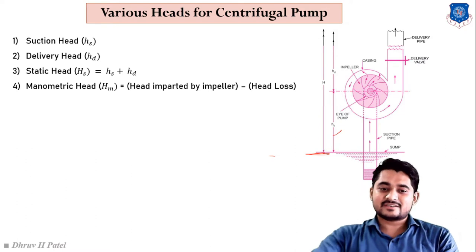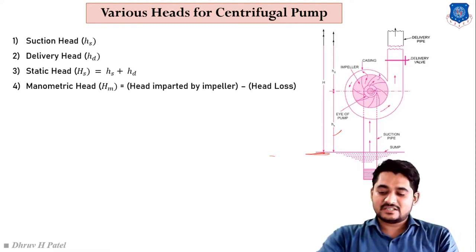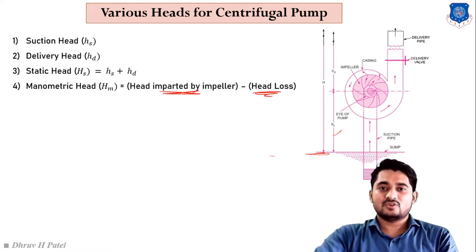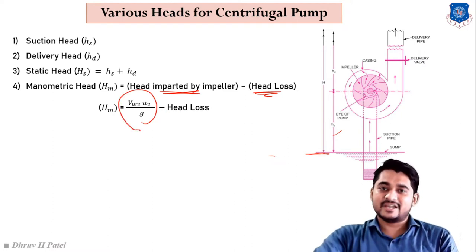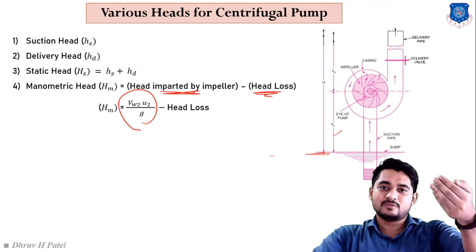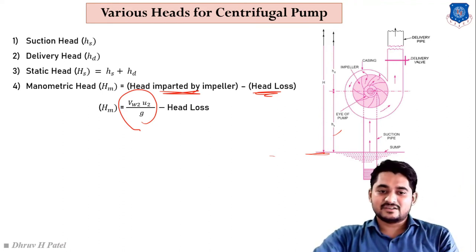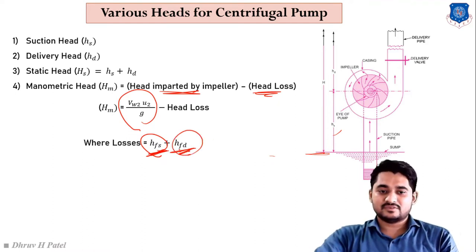Manometric head means the head imparted by the impeller in the ideal condition minus various types of losses. We can call manometric head the actual head delivered by the centrifugal pump. From our derivation, the head imparted by the impeller is V_w2 * u2 / g minus various types of head losses, which include friction losses in the suction pipe, delivery pipe, and impeller — represented as h_fs and h_fd.